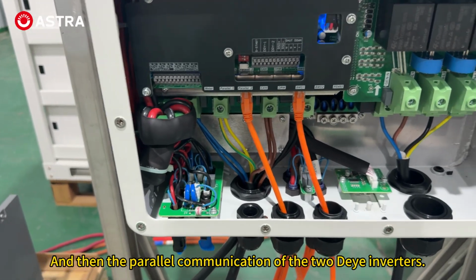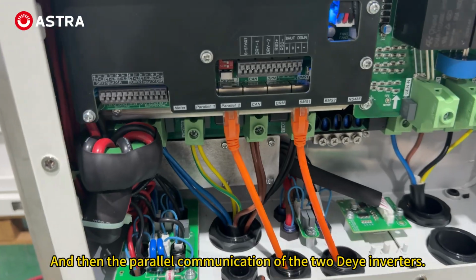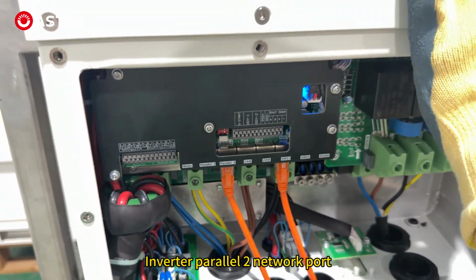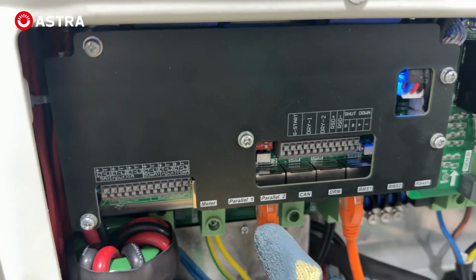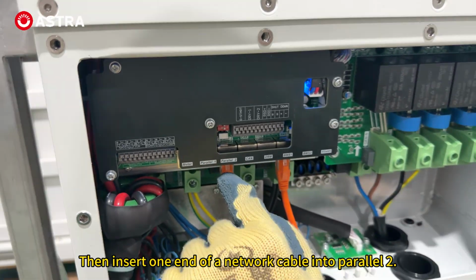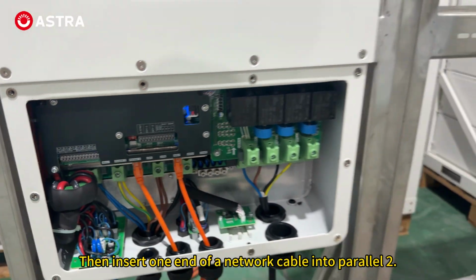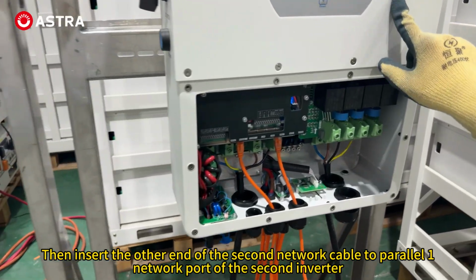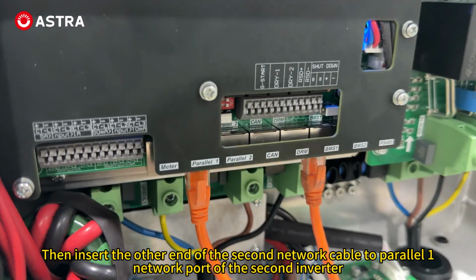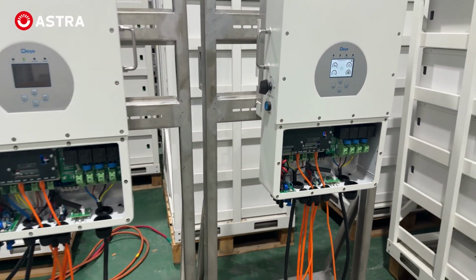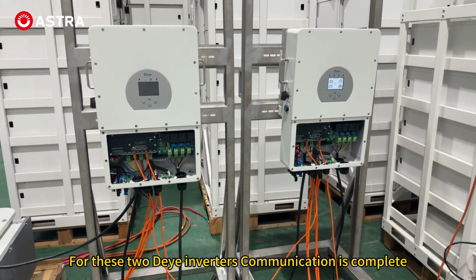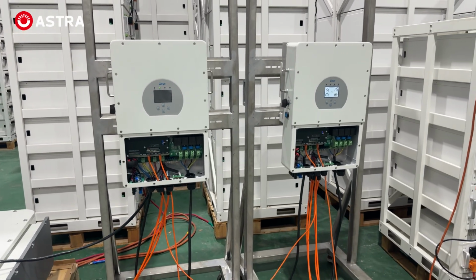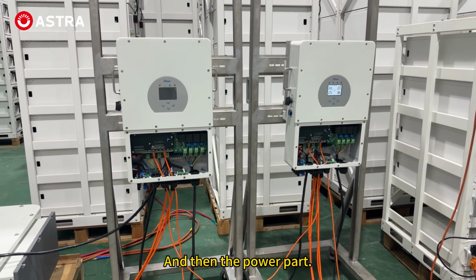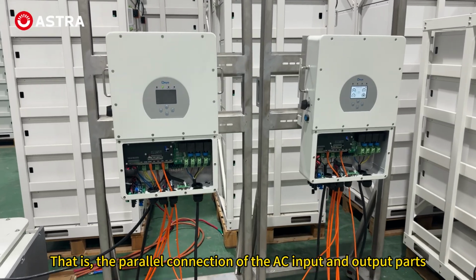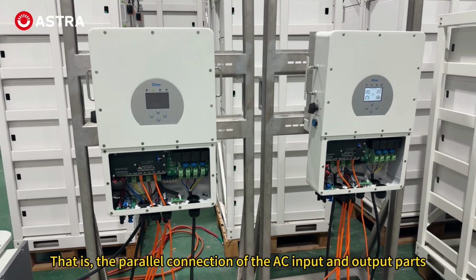And then the parallel communication of the inverters. Find the host, the first inverter's parallel network port. Then insert one end of a network cable into parallel 2. Then insert the other end of the network cable into the parallel 1 network port of the second inverter. For these 2 inverters, communication is complete. And then the power part, that is, the parallel connection of the AC input and output parts.